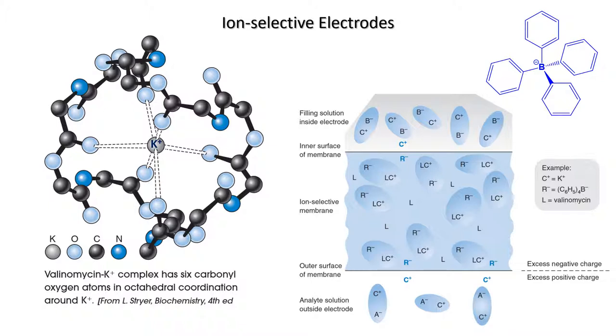The membrane contains a ligand which readily and preferentially complexes the analyte ion. The example of a ligand shown here is valinomycin, a ring-shaped molecule with inwardly directed oxygen atoms that complex potassium. The matrix in which the ligand is suspended is usually a hydrophobic polymer which rejects both water and water-soluble counter ions.